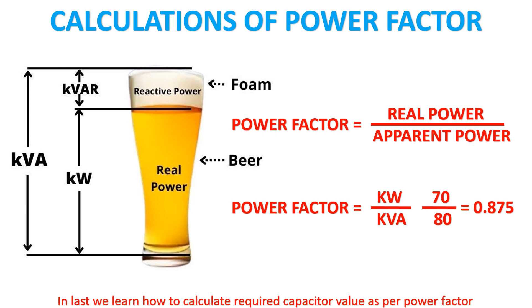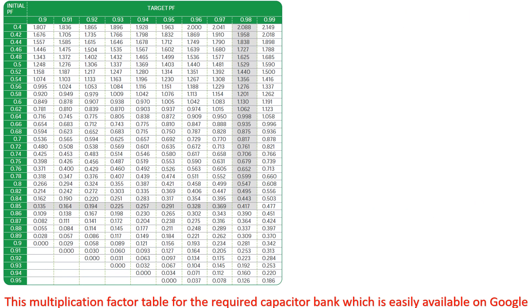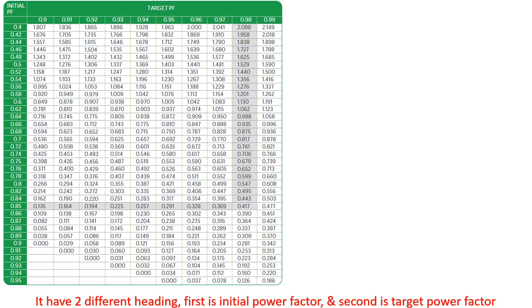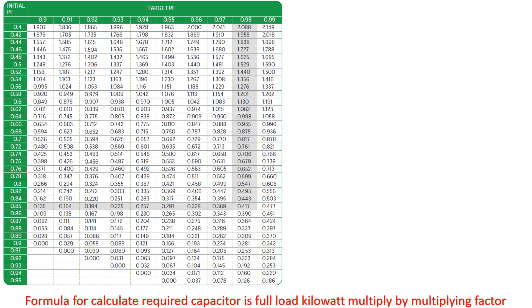Next we learn how to calculate the required capacitor value as per power factor. This is a multiplication factor table for the required capacitor bank, which is easily available on Google. It has two different headings: first is initial power factor, and second is target power factor. The formula to calculate the required capacitor is full load kilowatt multiplied by the multiplying factor.